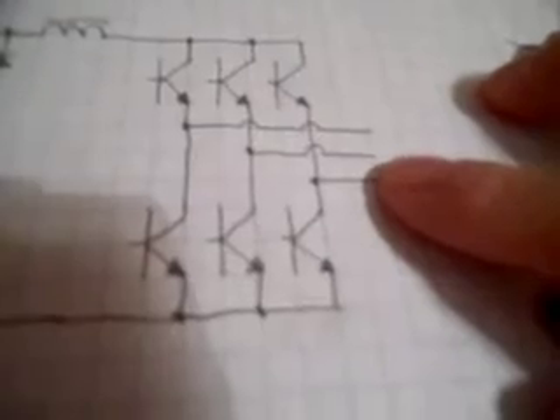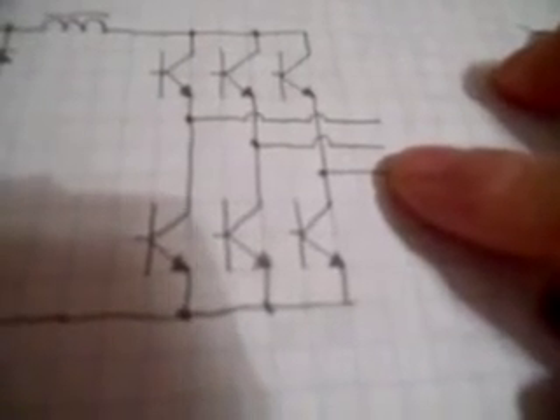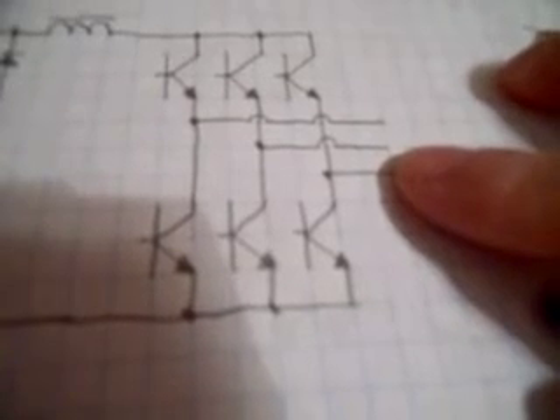If you took a standard 3-phase 60 Hz motor and you ran it up to 200 Hz, it could blow up in your face. If you take a dimmer light switch and you stick it on an AC motor, it's not going to change the speed at all. You need to change the frequency to change the speed in an AC motor. I mean, varying the voltage with a dimmer switch works great for a DC motor, but it's not going to work on an AC motor where you need to change the frequency.